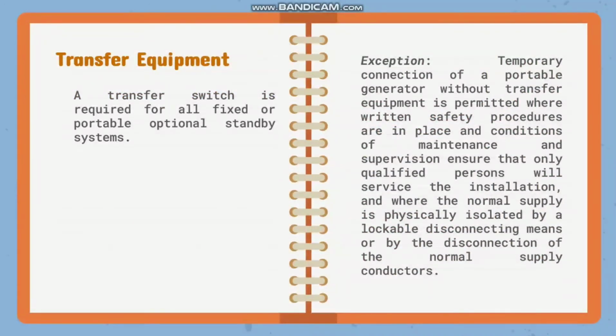For the transfer equipment, the transfer switch is required for all fixed or portable optional standby systems. Exception, temporary connection of a portable generator without transfer equipment is permitted where written safety procedures are in place and conditions of maintenance and supervision ensure that only qualified persons will service the installation and when the normal supply is physically isolated by a lockable disconnecting means or by the disconnection of the normal supply conductors.